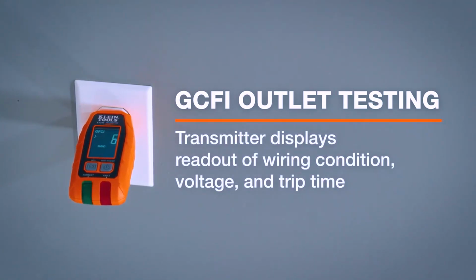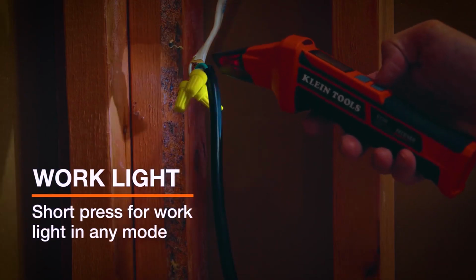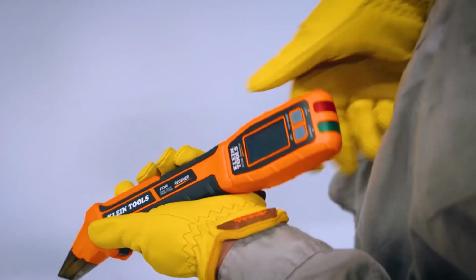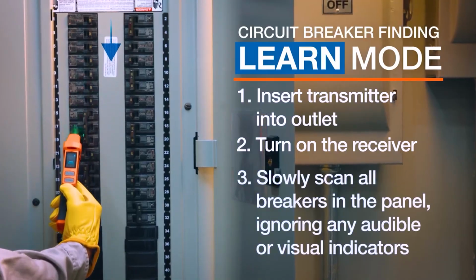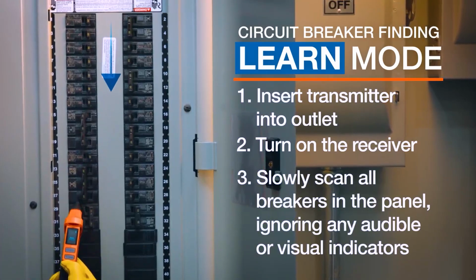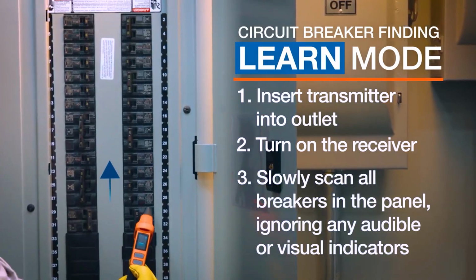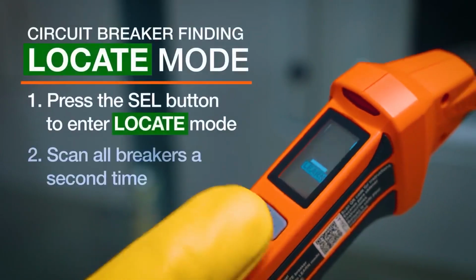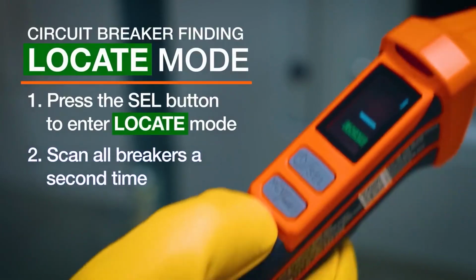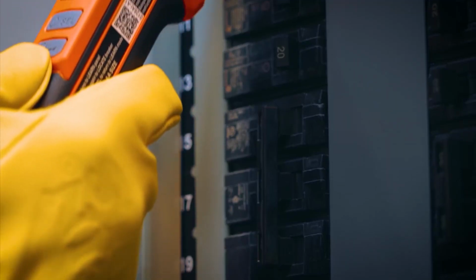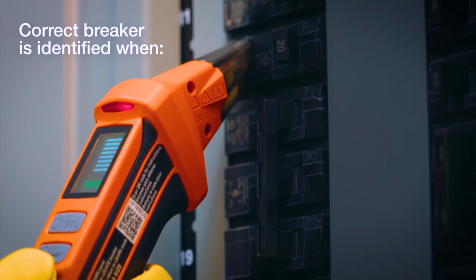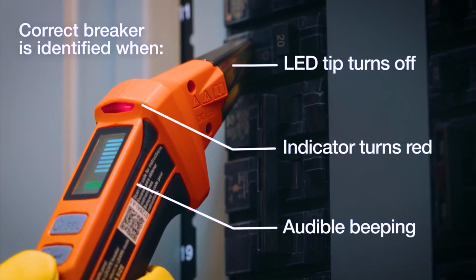It is more tool than some homeowners need, and simpler options may be faster for occasional use, but the diagnostic depth is excellent. The transmitter goes beyond basic outlet checking by displaying wiring faults, voltage, and ground fault circuit interrupter trip time. That last measurement is particularly useful when you care about how the protection device actually responds, not merely whether it trips at all.